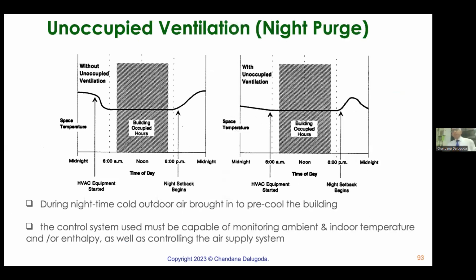Next one is unoccupied ventilation night purge. We can have air handling units run during night, maybe early morning, when the air temperature is colder, 24 degrees, 22 degrees. Run the air handling unit only to circulate air. Actually, you take 100% fresh air, blow it through the building and exhaust. That will chill the building and reduce the energy consumption.